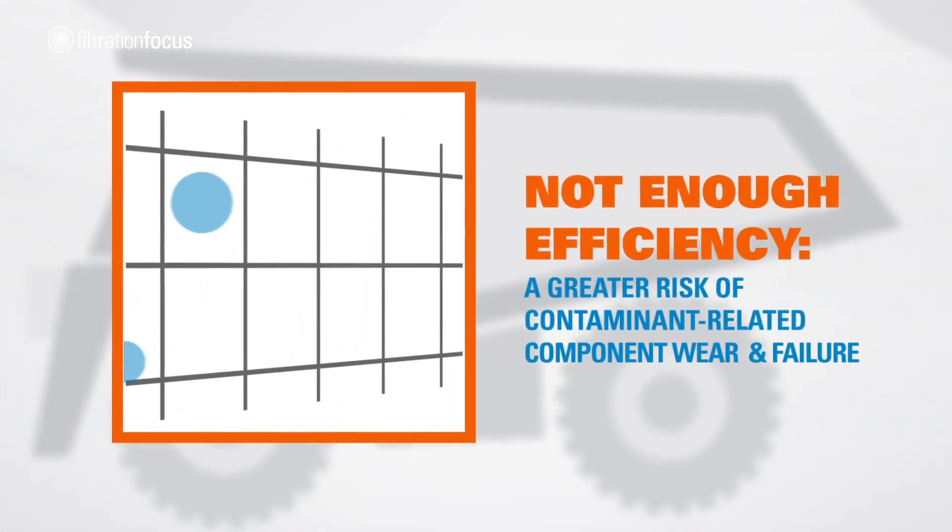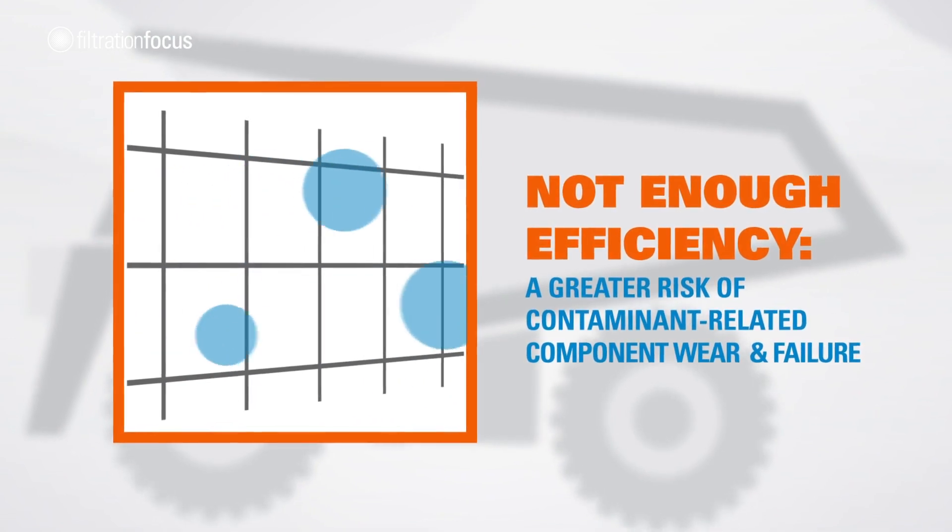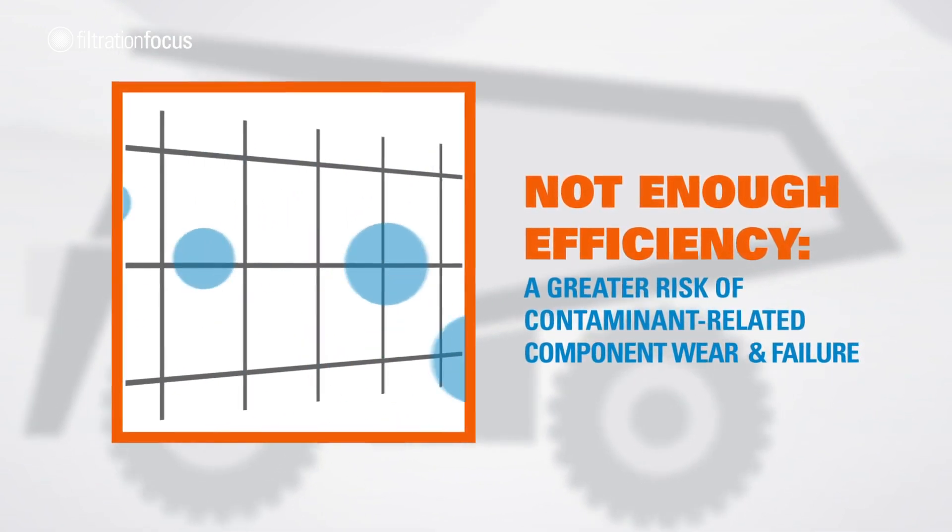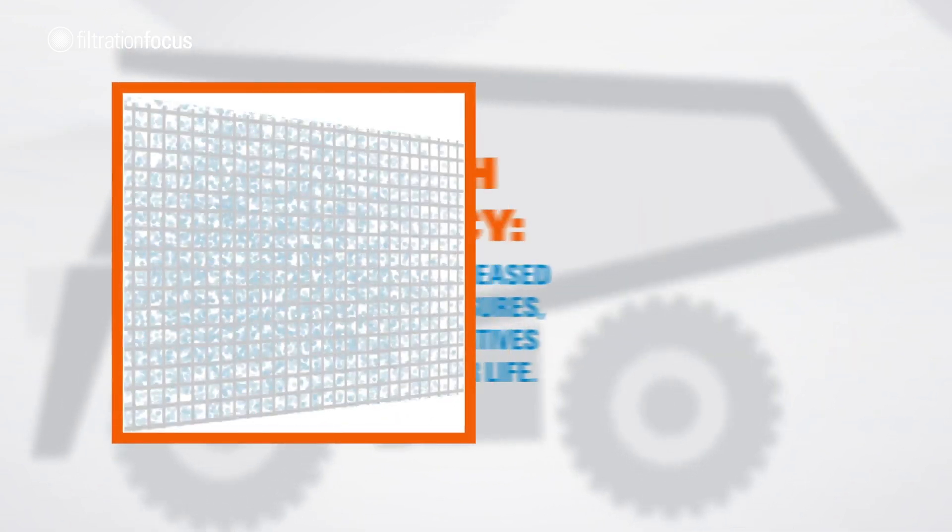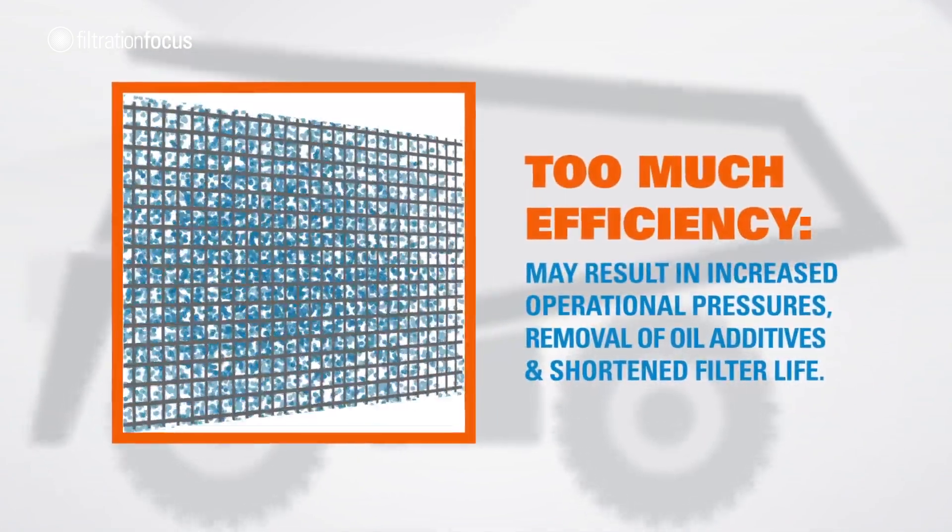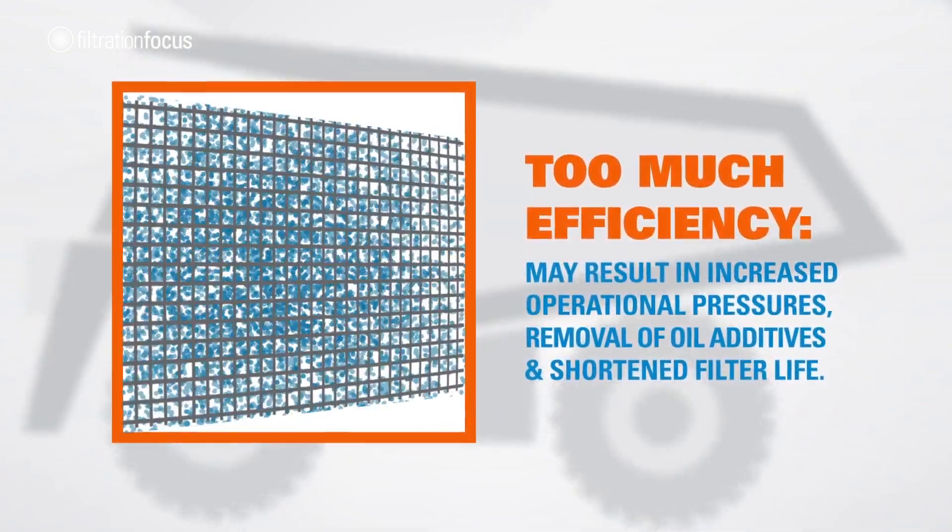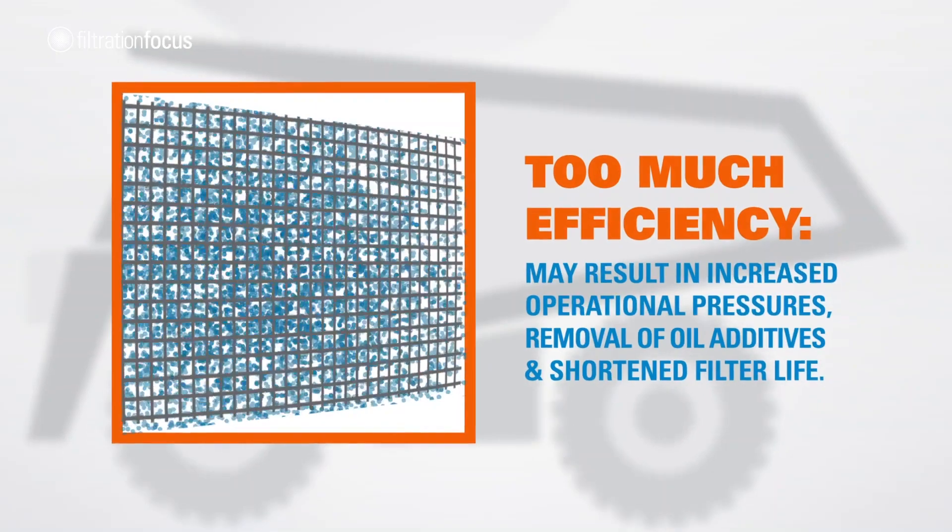Not enough efficiency leads to a greater risk of contaminant-related component wear and failure. Too much efficiency may result in increased operational pressures, removal of oil additives and shortened filter life.